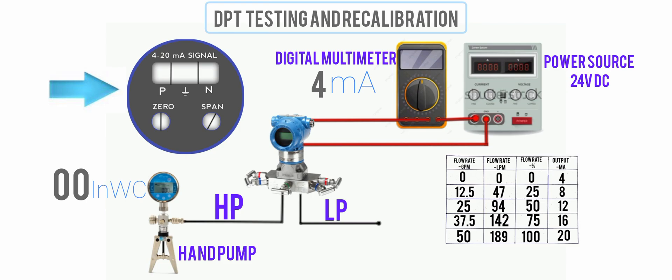Apply the 100 percent input pressure value, which for us is 200 inches water column, to the transmitter and adjust the span until we get an output current of 20 milliamps. Repeat the steps until adjustments are no longer required.